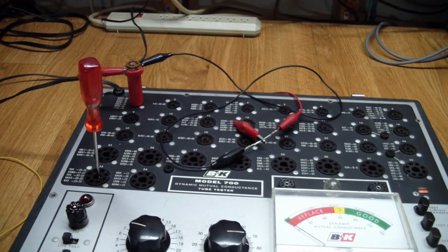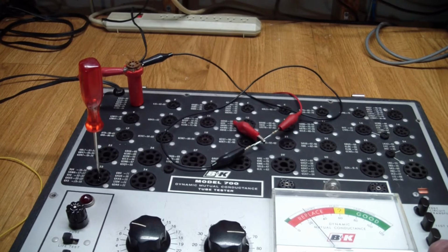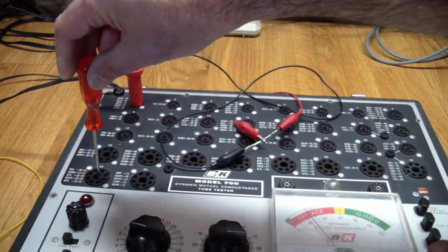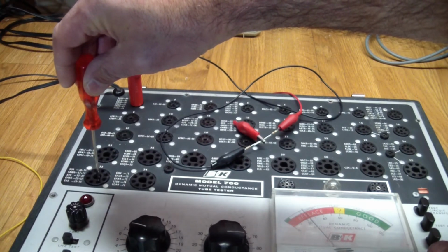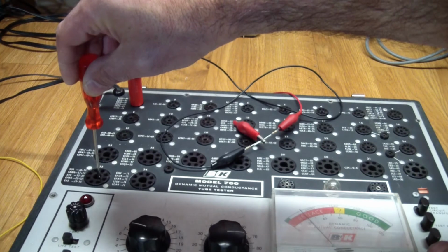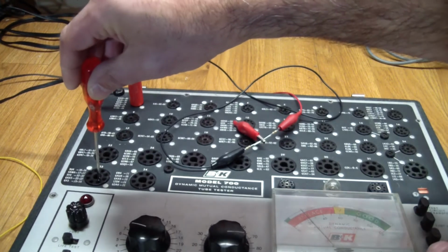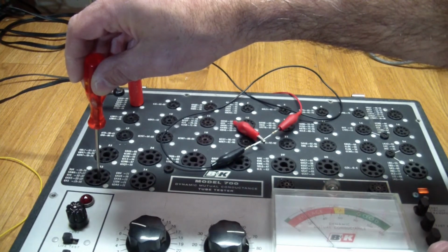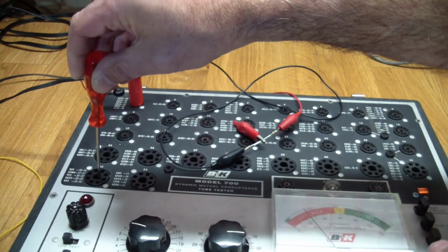The second calibration step is the grid emission sensitivity adjustment. For that, we hook up 20 megohms between pins 1 and 6. I used two 10s because I didn't have a 20, and use the pot accessible through socket 33 to adjust the grid emission so that the meter goes to 20, and with the glare you probably can't see it, but 20 is right over here. So when I press the grid emission, it goes a little bit above 20, and all we've got to do is adjust it in the right direction. The meter doesn't have a mirror scale, so it's a little bit harder to adjust, looking at it right from the top and putting a shadow there, but come on.